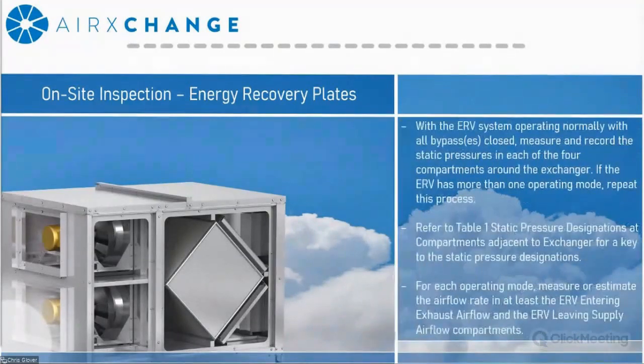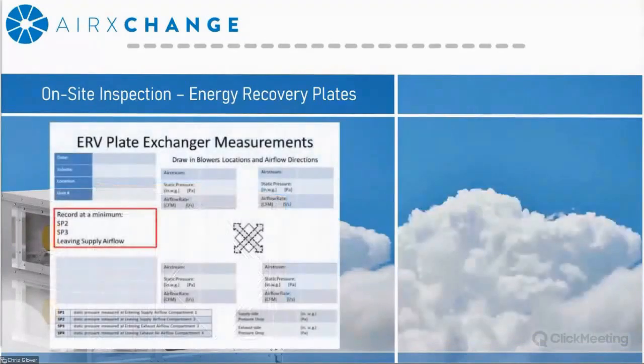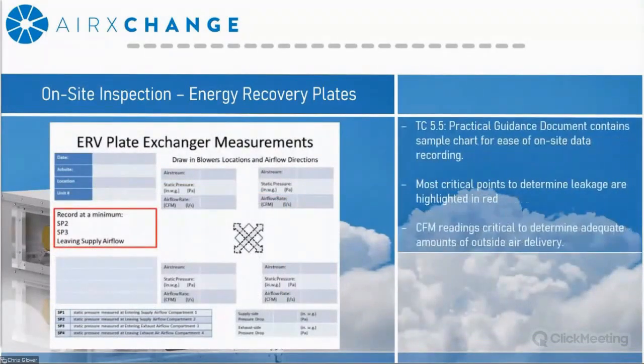Okay, so the second part is turning the system back on. And once again, you're going to follow a similar model. You're going to take the static pressures in all the 4 quadrants that surround the component. If your system has more than one operating mode, once again, repeat this process for all the operating modes. And just like wheels, within that TC 5.5 document, there's going to be a sample chart used for plate-based products. Once again, the critical points to determine leakage are highlighted in red, and the CFM readings, which are critical to determine the airflow, should be taken at this point in the process.